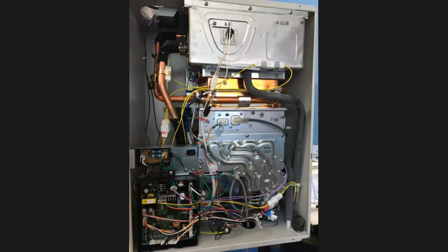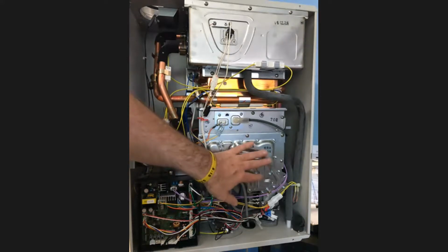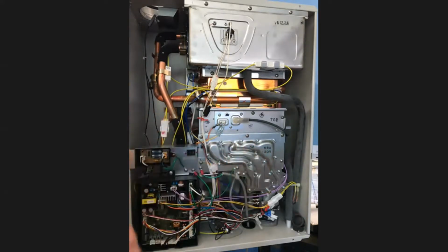To make sure we're not sending out a temperature that's too hot, the unit does this itself. It modulates not only that bypass valve, but also the burners through the gas valves, to hit the target water temperature going out.